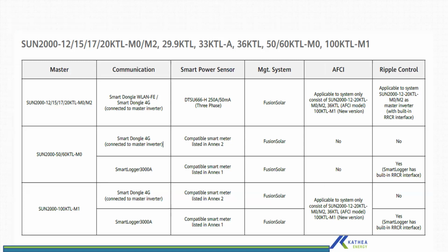So the management system is the same for all the inverters from the 12 to 100 KTL, which is the Fusion Solar. The arc fault, the 12 to 20, the current versions on the market already have built-in arc fault detection. And the 100 KTL M1 already has it built in. The 50 and 60 KTL inverters, the newer version, which is the M1, will be ready for the market in Q2 to Q3.